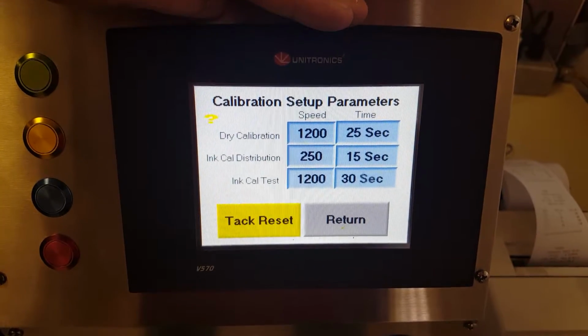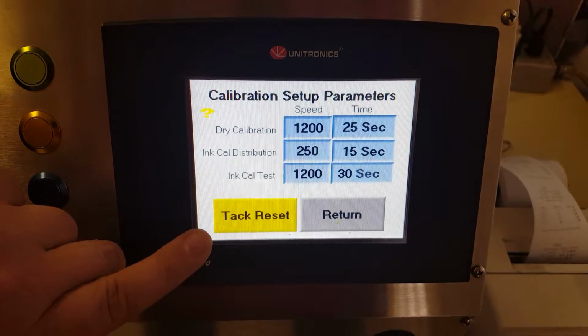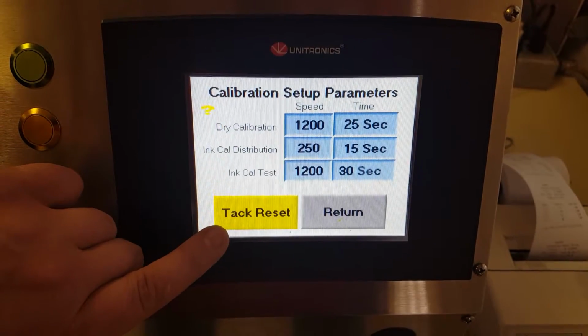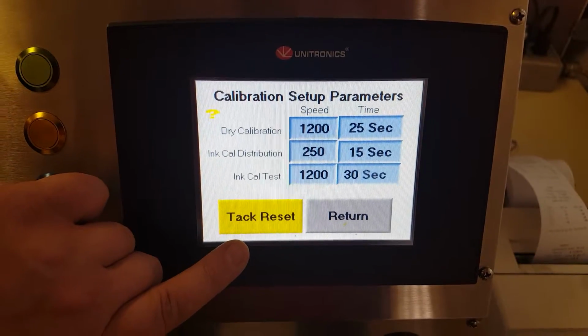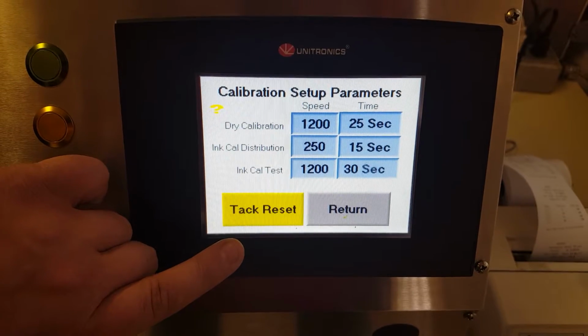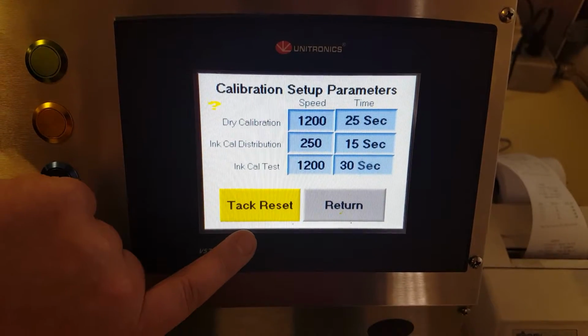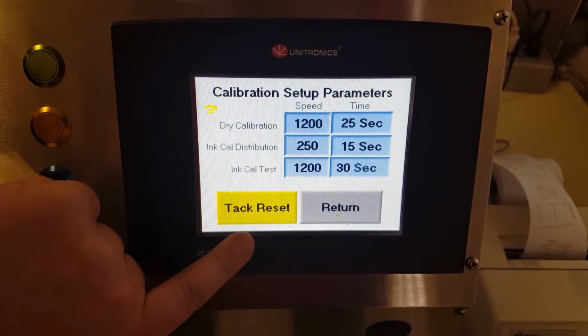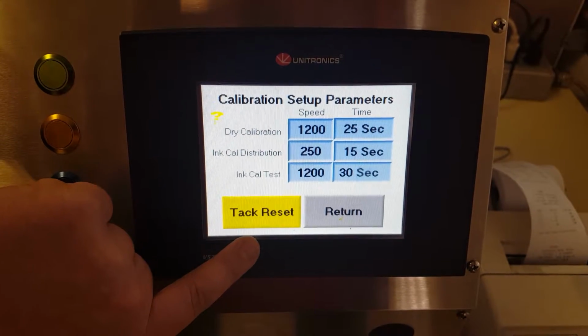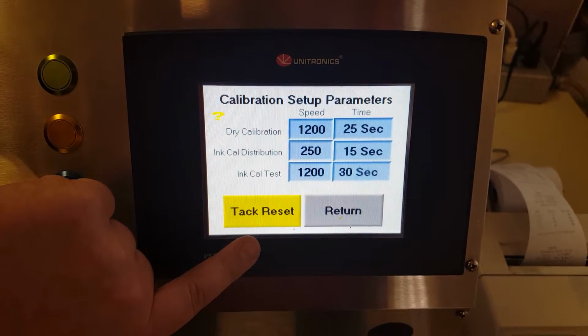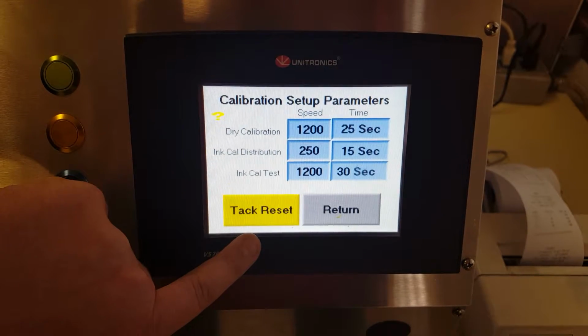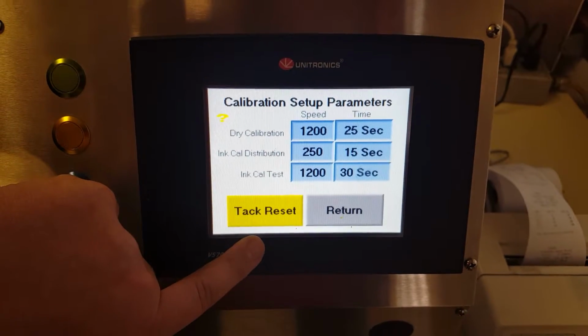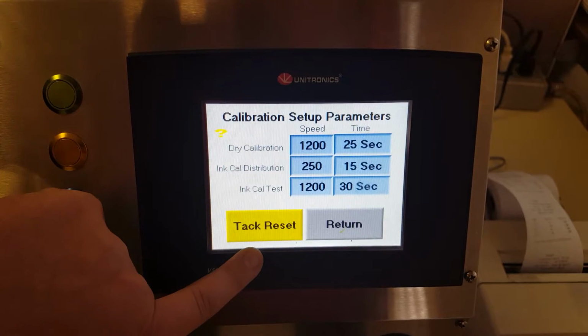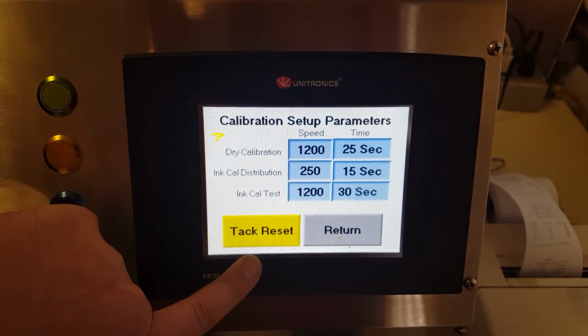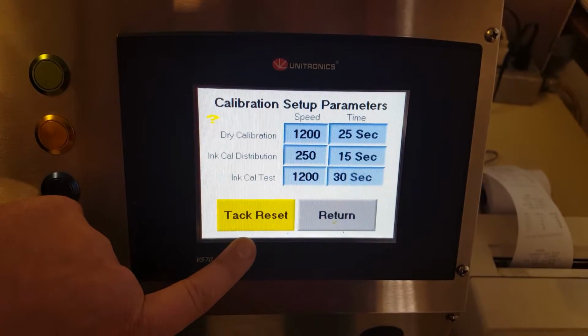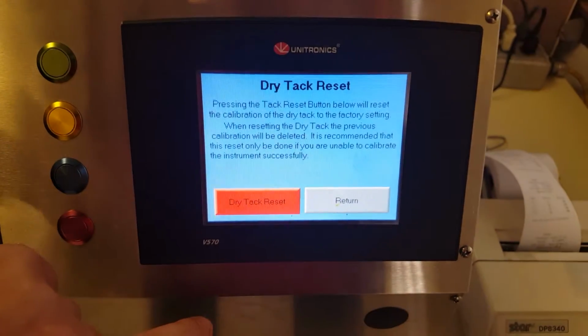Pretty straightforward. Now, on the bottom here, you'll see a yellow rectangle on the bottom left-hand side of the screen, and it says Tack Reset. The purpose of that is basically to avoid any major catastrophes with Tack calibration issues, if you have any. A lot of times these calibration numbers will get out of whack for whatever reason, and instead of breaking your back going through all the calibration parameters and trying to set things up, sometimes it's easier just to set it back to factory settings, which is exactly what we can do by pressing that button.